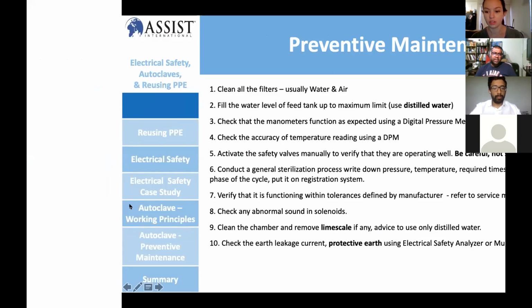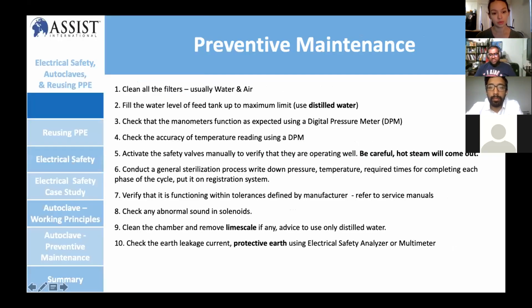So there's a different type of electrical safety analyzer. It depends on the model. Some brands have fully automated standalone machines. Some use software through your laptop, and you can automate them. So it depends. The model that we showed earlier normally runs manually. If you want to automate that particular device, you need to run a different program, but normally it's not advisable actually. Very good.